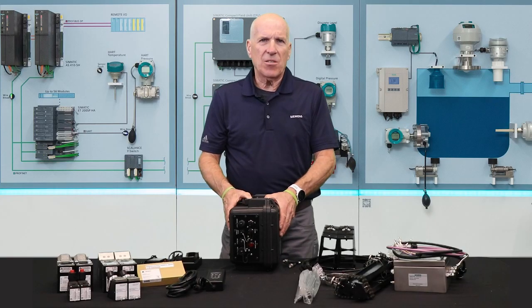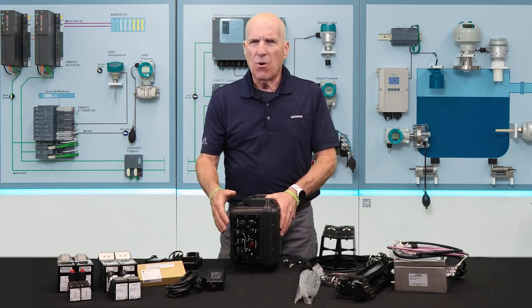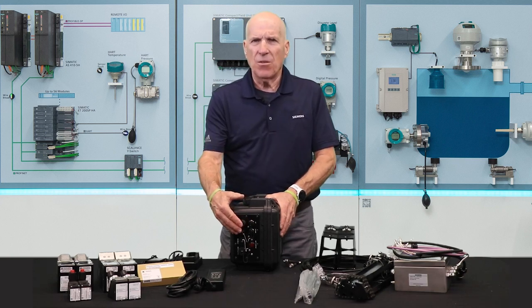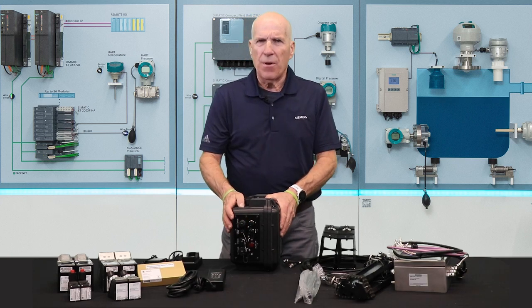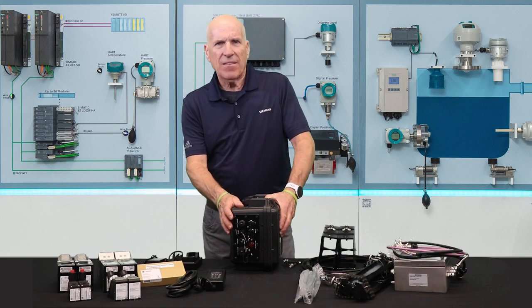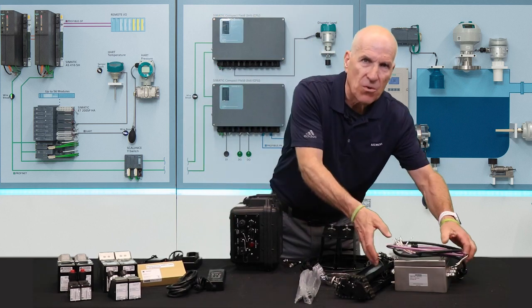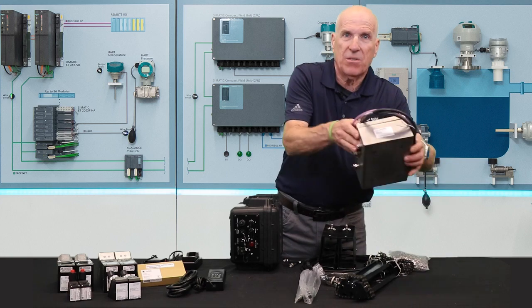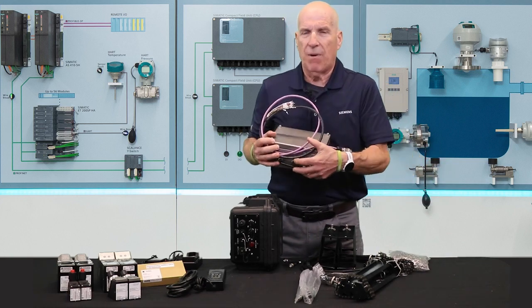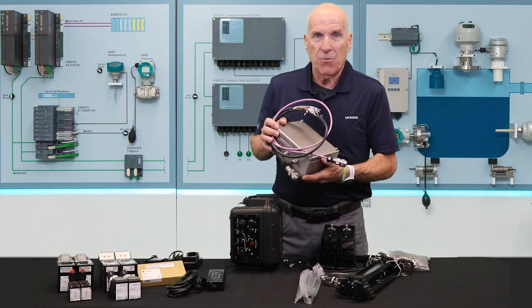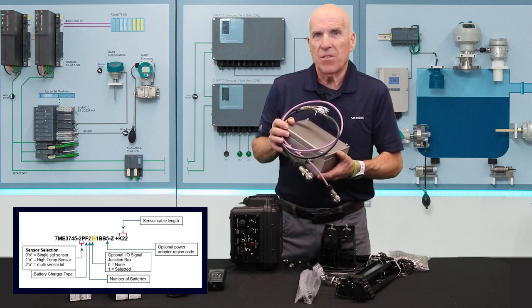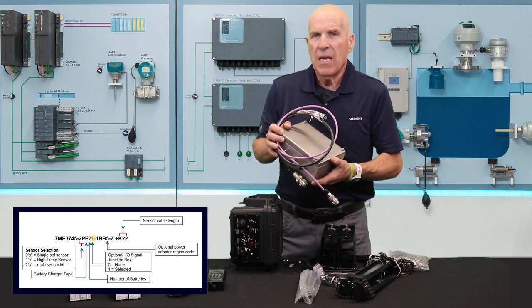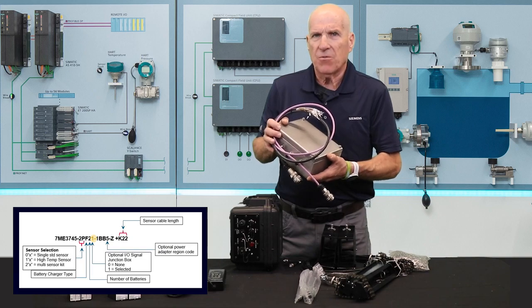The FS290 is supplied in an IP67 weatherproof case. The IP67 rating is maintained when the I/O connections are capped when not in use or connected using appropriate cables. For this reason, to access any of the analog I/O terminals or digital communications via Modbus, a special connection junction box is available. If this option was ordered, position 12 of the system part number will indicate a 1, and you will receive this junction box for termination of your output wiring.